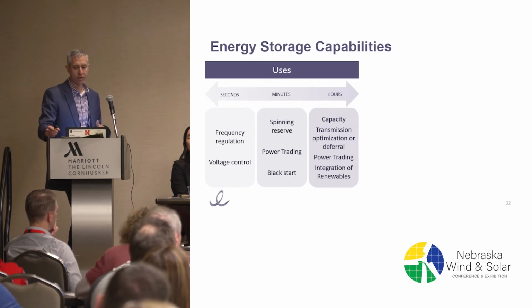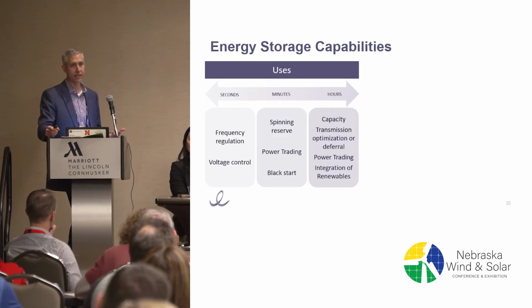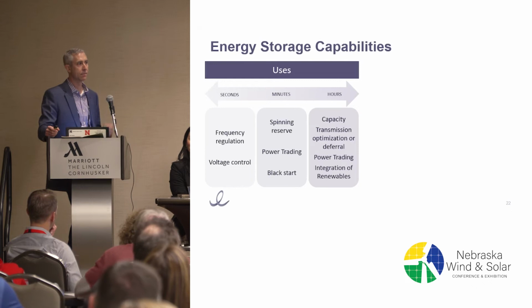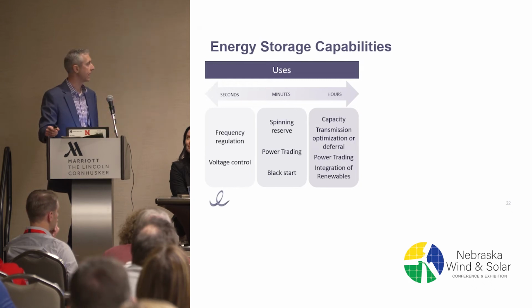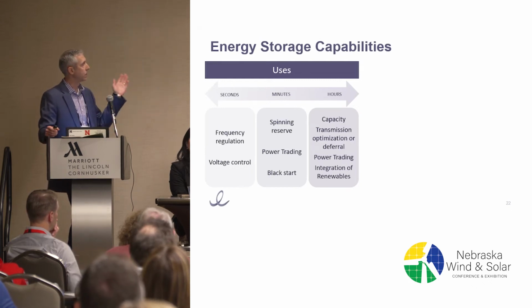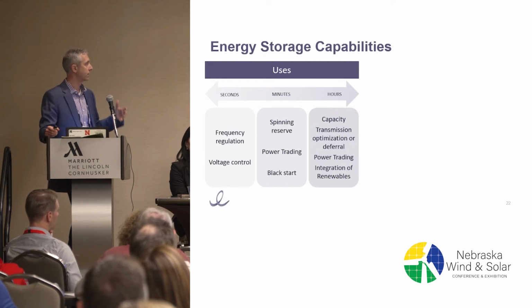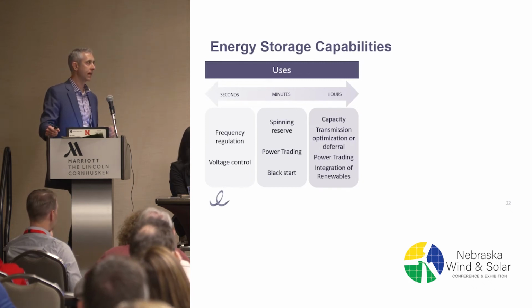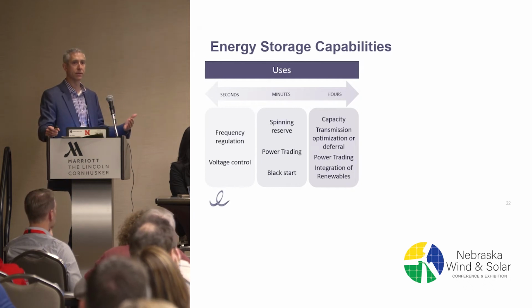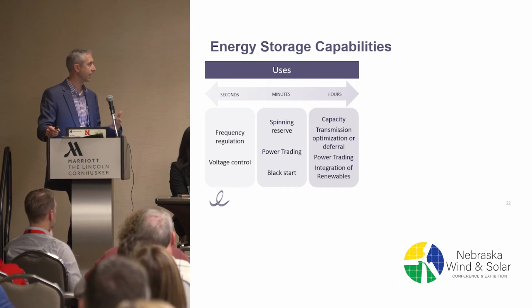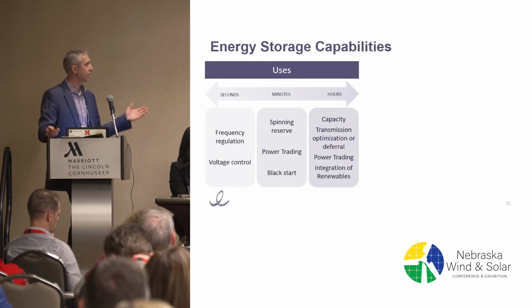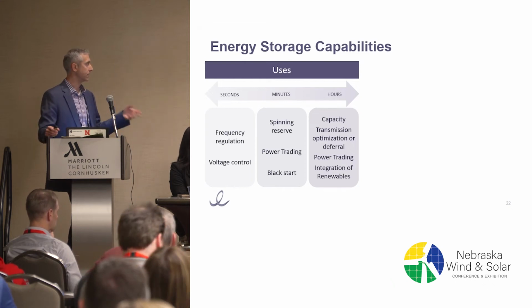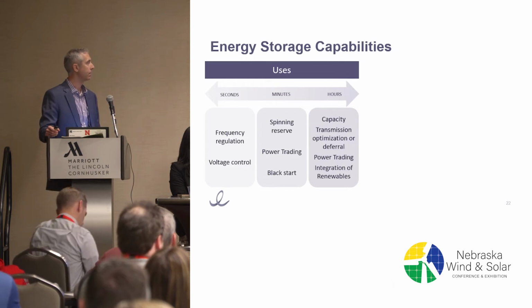One of our ERCOT projects was originally specified to have a response time of 250 milliseconds and a very rapid set point onto a ramp rate that was established. Then you have your minutes resource, sort of spinning reserves, other ancillaries, potentially black start, though it would be false advertising to say that all energy storage projects can do black start. That's a special capability that's usually built in after the fact. And then as you get to the hours, you're in the place of power trading and capacity and integration of renewables.